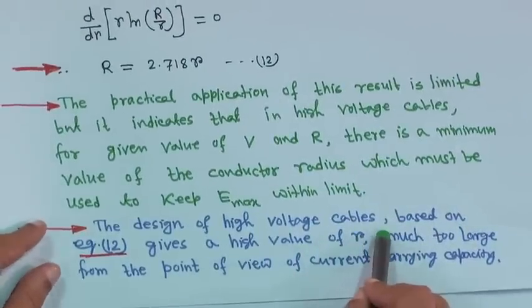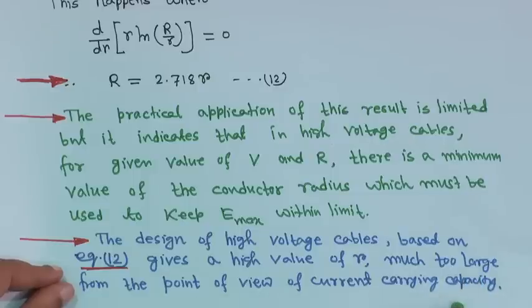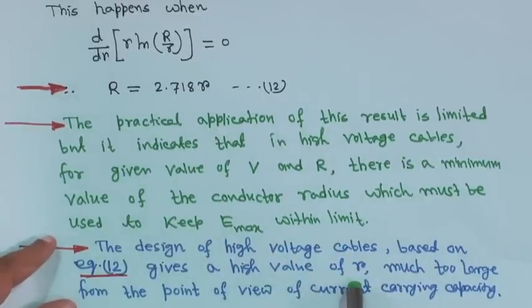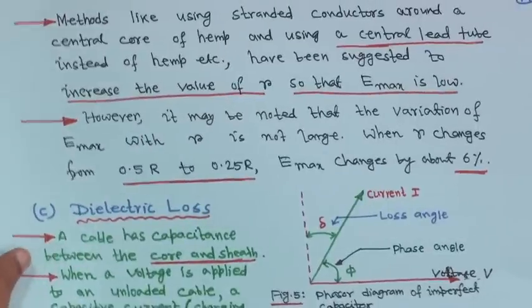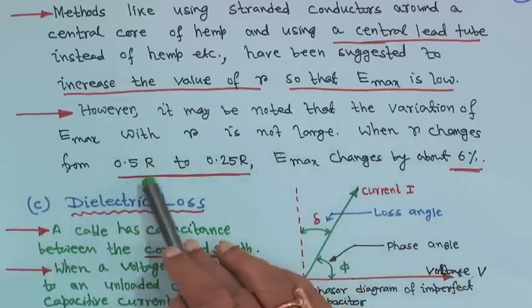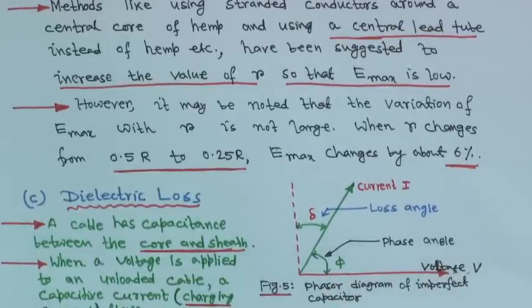The design of high voltage cables based on this equation gives a high value of r which is much too large from the point of view of current carrying capacity. Methods like using stranded conductors around a central core or using a central lead tube instead have been suggested to increase r so that E_max is low. However, the variation of E_max with r is not large — when r changes from 0.5R to 0.25R, E_max changes by only about 6 percent.